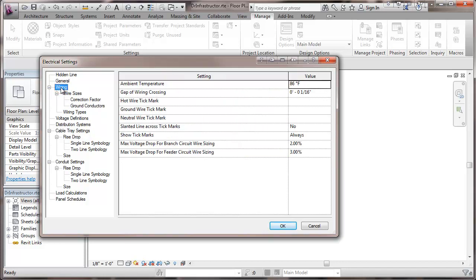And I'm going to cover wiring. This one we have ambient temperature which is used in calculations of capacity, what size gap there is in the wiring when one wire crosses another and they're not connected. Particularly important is for the tick marks for when we're doing circuiting, showing the number of conductors, hots, neutrals, grounds. And here we can choose exactly what is used as the tick mark and hopefully conform to some standards that are being used in drawings elsewhere.